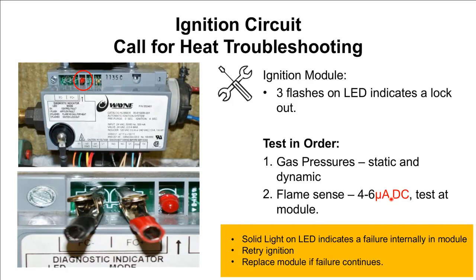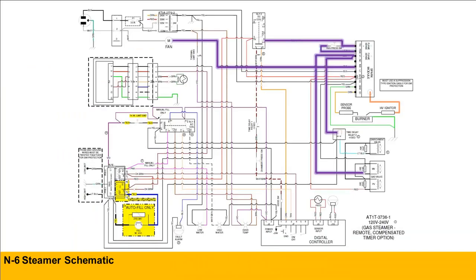So some equipment, you actually have to put your meter in series because amps can only be checked in series. Not with this module. At this point, if there's no existing flame sense, more than likely it's going to be the module, because even if the flame sensor is going bad, unless it's completely broken, you should get something. But if there's nothing, 0, you more than likely have a bad module. But if we're not sure, we might even just say take both parts with you just in case, and obviously starting with the module first. So once again, power comes in, hit your blower. From there, we'll start the ignition sequence, open your main valve, at the same time sending power to your igniter.